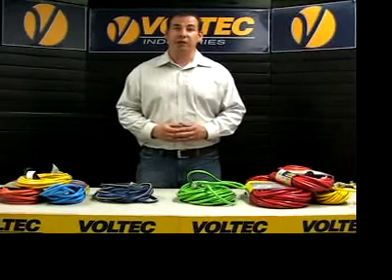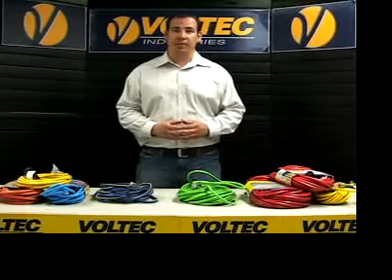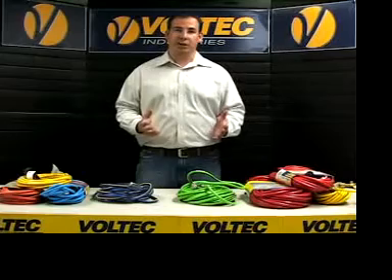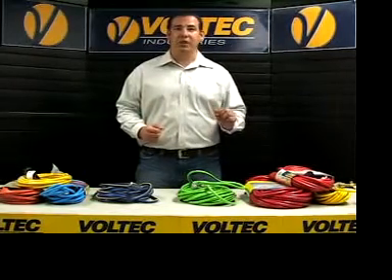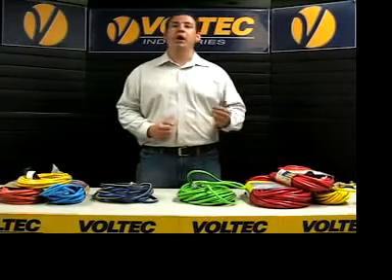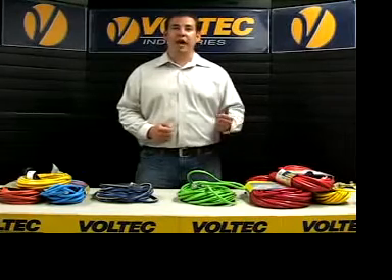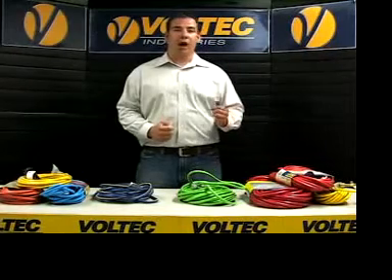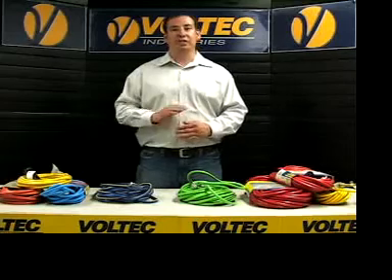Job sites can be shut down or even fined by an OSHA inspector if a non-UL cord is being utilized. Non-UL-approved products can vary wildly in performance and durability characteristics, with less than desired power being supplied and potentially hazardous material failures. When purchasing a cord, you should look for a UL number, which will be E followed by six digits on the jacket of the cord, and a label at one end of the cord. The label should be blue or holographic. If these items are not on the cord, then the cord is not UL listed.